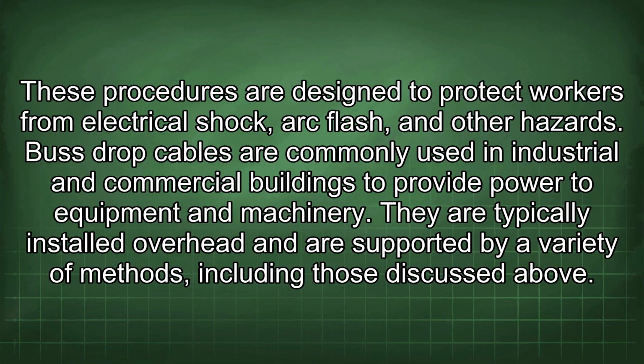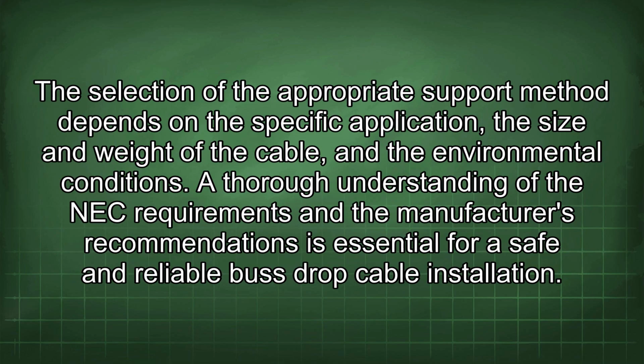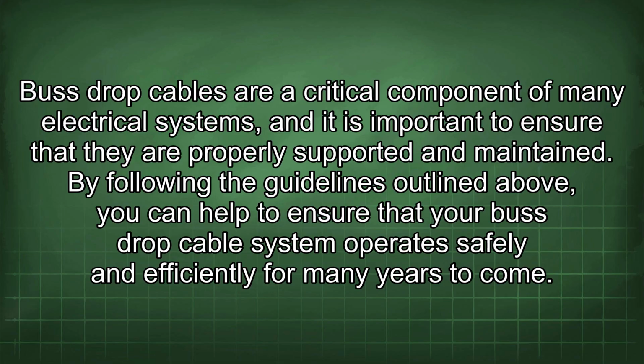Bus drop cables are commonly used in industrial and commercial buildings to provide power to equipment and machinery. They are typically installed overhead and are supported by a variety of methods, including those discussed above. The selection of the appropriate support method depends on the specific application, the size and weight of the cable, and the environmental conditions. A thorough understanding of the NEC requirements and the manufacturer's recommendations is essential for a safe and reliable bus drop cable installation. Bus drop cables are a critical component of many electrical systems, and it is important to ensure that they are properly supported and maintained. By following the guidelines outlined above, you can help to ensure that your bus drop cable system operates safely and efficiently for many years to come.